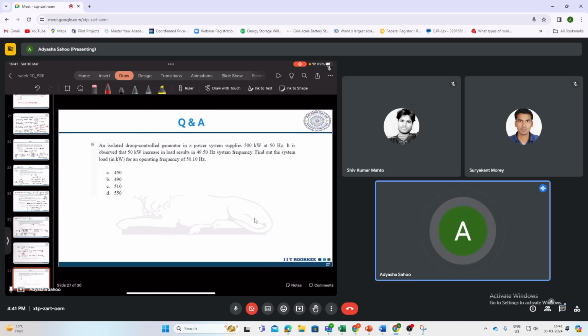Now an isolated droop-controlled generator supplies 500 kilowatt at 50 hertz. It is observed that a 50 kilowatt increase in load results in a system frequency of 49.5. Find out the system load for an operating frequency of 50.1.